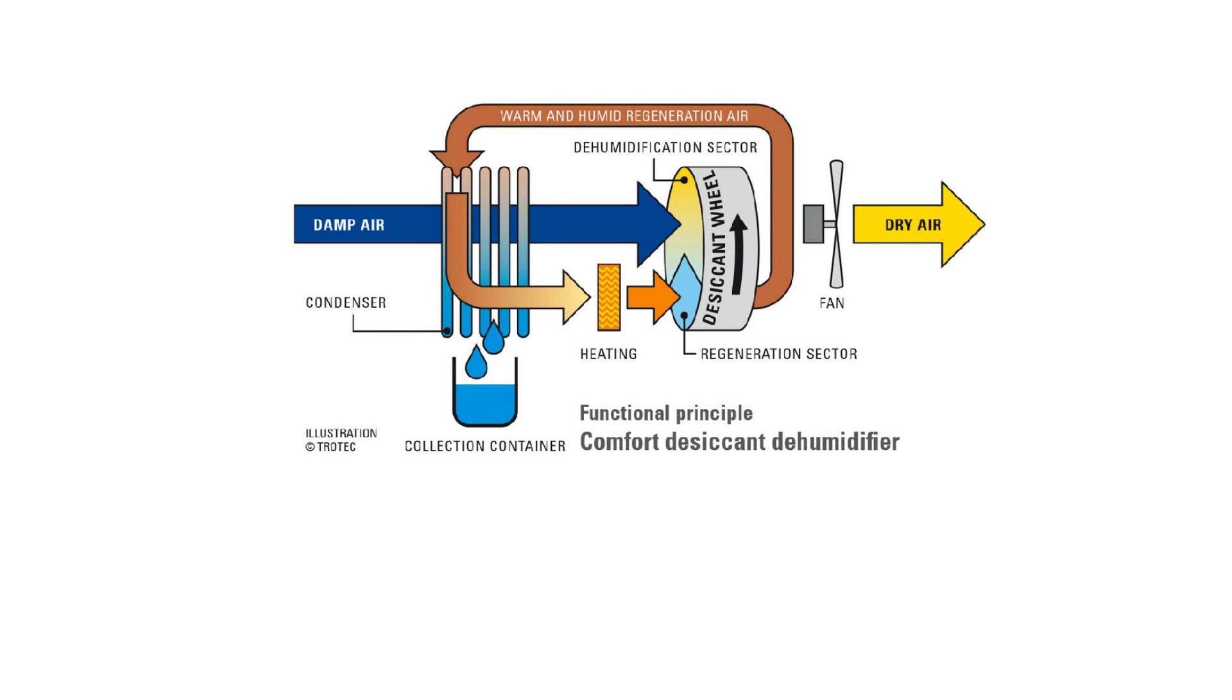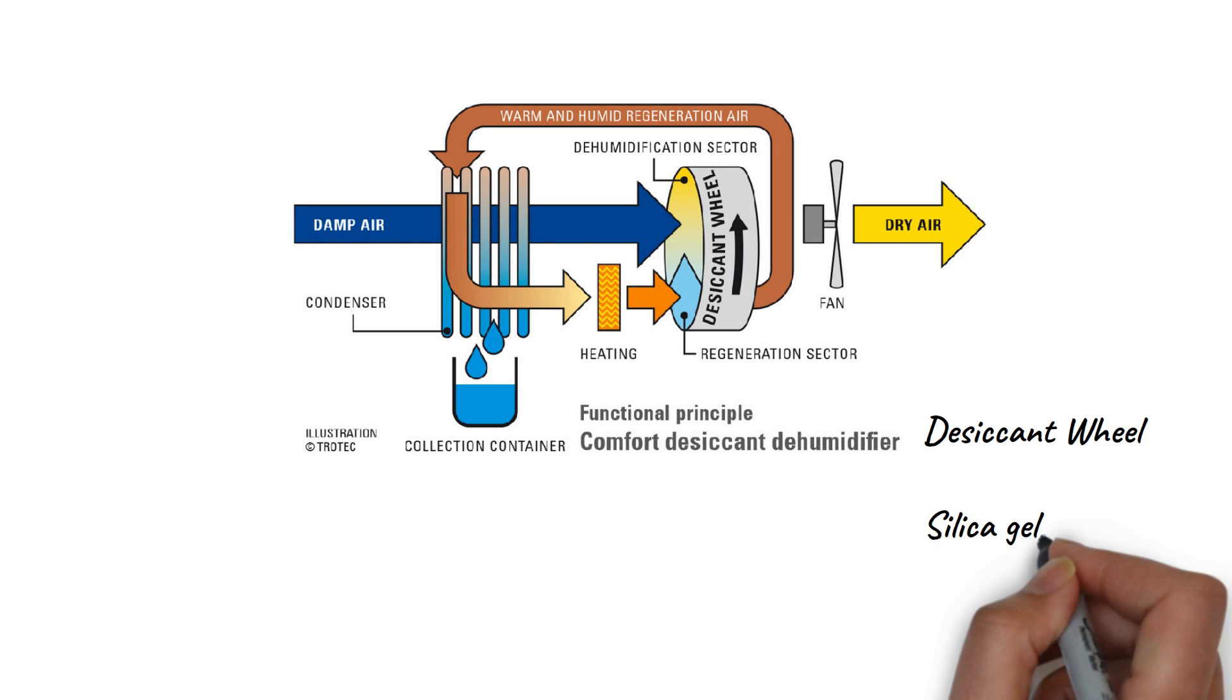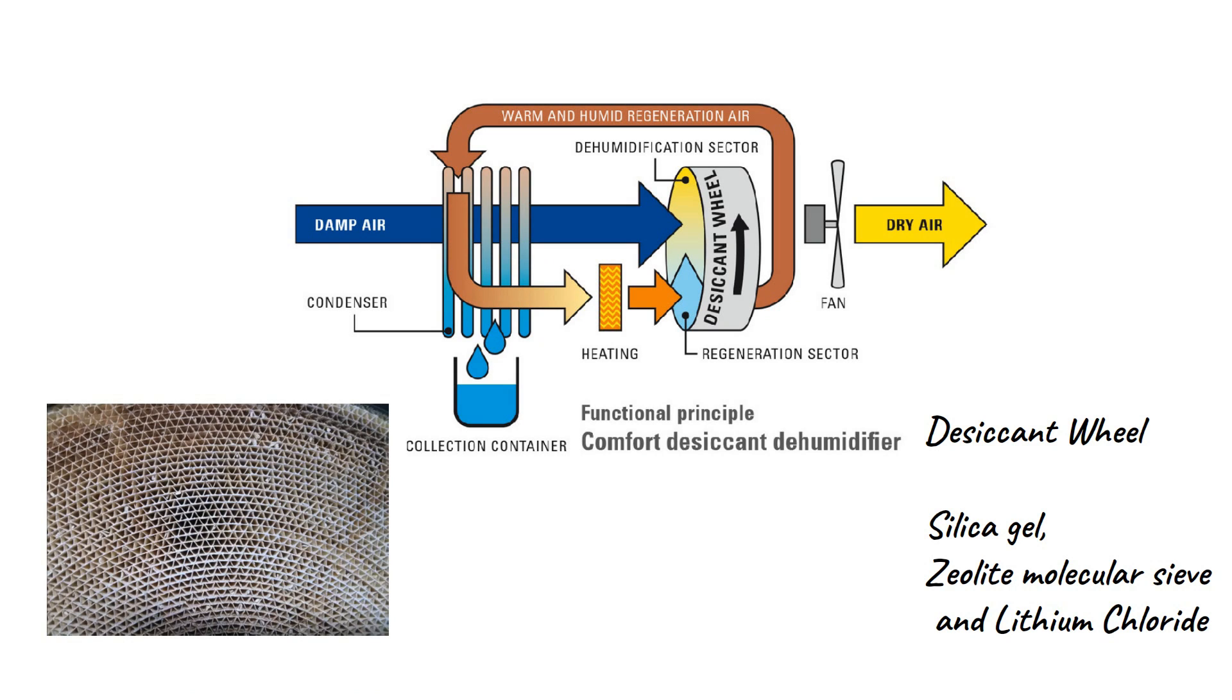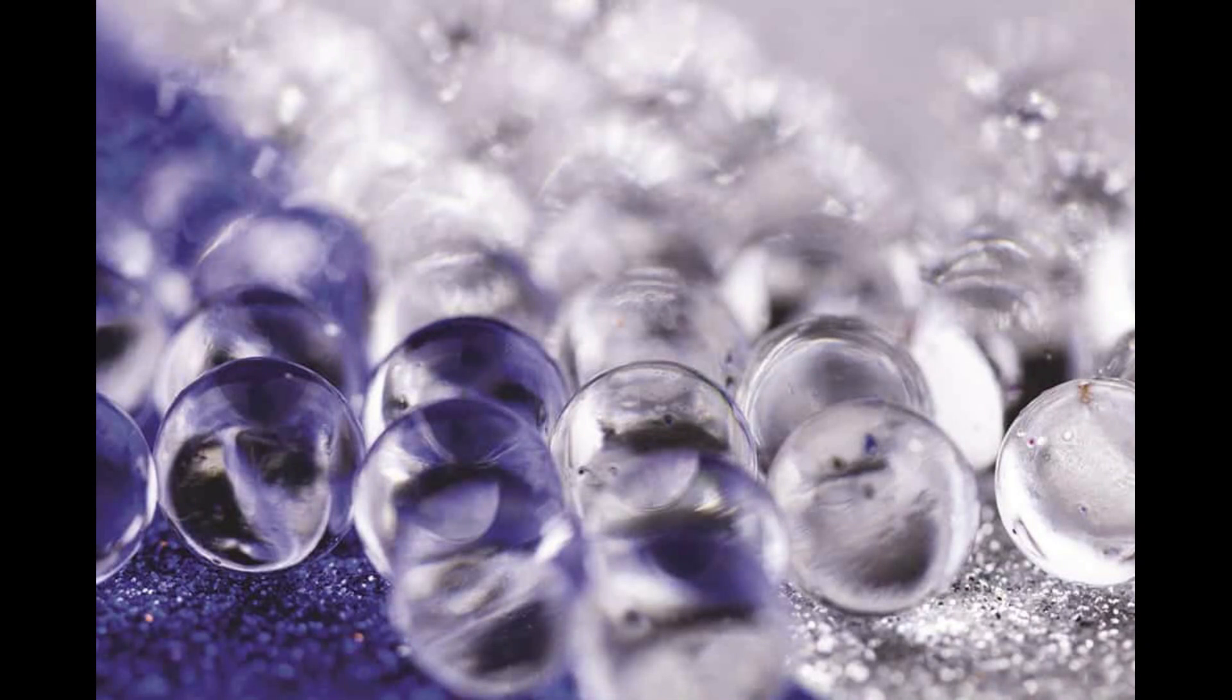Humid air is sucked and is passed through a desiccant wheel. The commonly used materials in desiccant wheels are silica gel, zeolite molecular sieve, and lithium chloride. These materials are hydrophilic, that is, once the humid air passes through them, they remove the moisture and dry air is left behind.